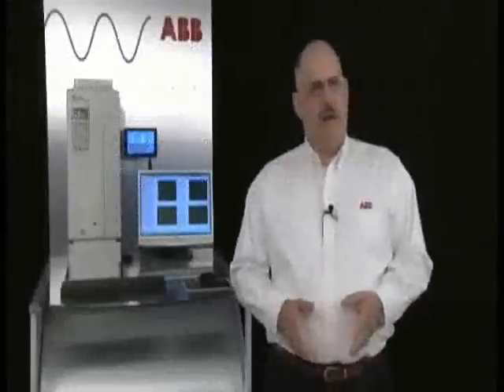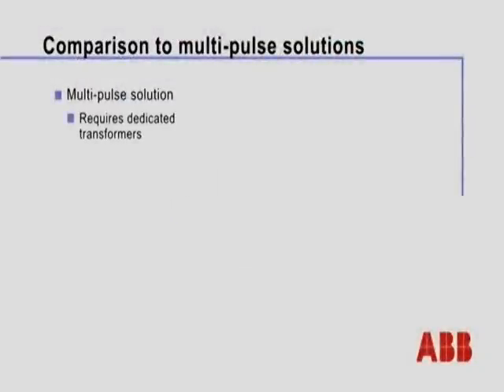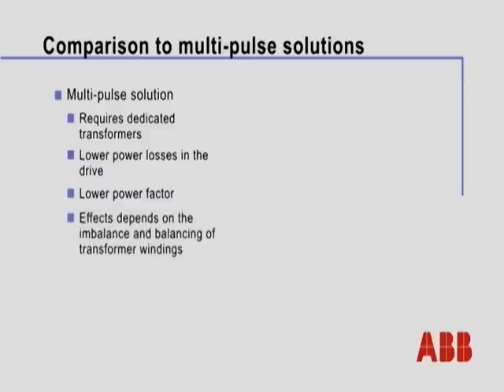I'd like to take a minute right now to compare the multi-pulse solutions to the ULH. The multi-pulse solution requires a dedicated transformer in order to achieve its multi-pulse goal. While the drive itself has lower power losses, the overall efficiency is equivalent to the ULH drive. There's a lower power factor in a multi-pulse solution, which, while almost unity, doesn't quite get there. And the effectiveness of this solution depends upon the line balance or imbalance of the incoming power, as well as the balance of the transformer that's being used.